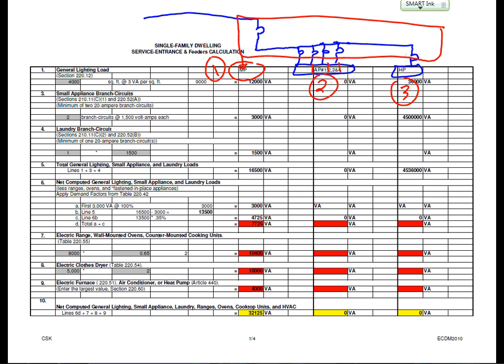So Matt, when we were talking about the common panel, which feeds everything, the house panel, they call it common panel, right? Or panel 5, we call it. How are you going to size that panel 5? Is it going to be 100 amp, 200 amp, 300 amp, 500 amp? That's what the load calculation is supposed to do. It's supposed to get you an amp size for your equipment. Can I get you guys to understand what this is supposed to do?